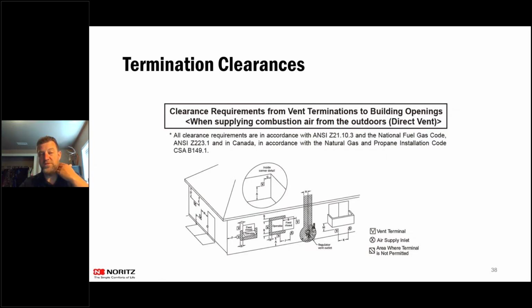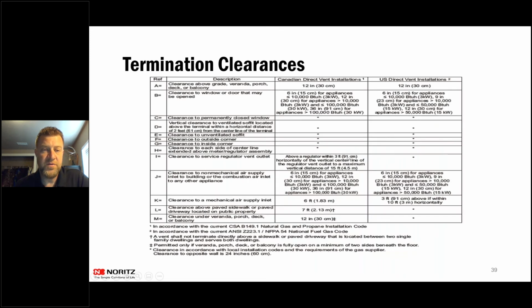Venting clearances. Within the National Fuel Gas Code, there are venting clearances to everything that's in there. This is the actual table here. On the first one, in A, this is clearance above grade, veranda, porch, deck, or balcony. When you're looking at these forms, make sure you're looking at the US and not the Canadian side. Always make sure you're looking at that US. So the clearance above grade, which is coming out of the house, here it's saying 12 inches above the grade, veranda, porch, deck, or balcony. They want you at least 12 inches up off the ground on that.